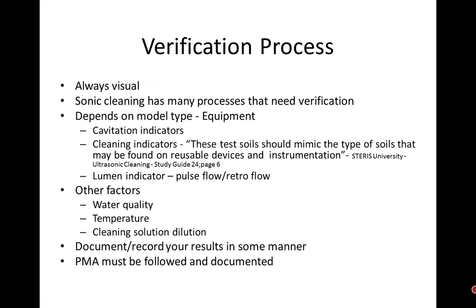In most of the cases, the majority of the cases, it is blood. And also, if you have a pulse flow lumen, and we're going to talk about that, those pumps are actually working. And I'm going to show you examples of where pumps have not been working and talk about it. Other factors, you should look at the frequency of water quality, your temperature. Are you getting the right dilution? That is very important. If not, and you're expecting to have 1 ounce per gallon, 1/4 ounce per gallon, or whatever it is, and if you're not getting it, you're not going to have the cleaning you think is going to take place. As always, document, record your results when you do verification, and that preventive maintenance agreement must be followed and documented. Quarterly, weekly, monthly, whatever it is, if you don't keep that sonic in good working condition, it's not going to produce the results you want.